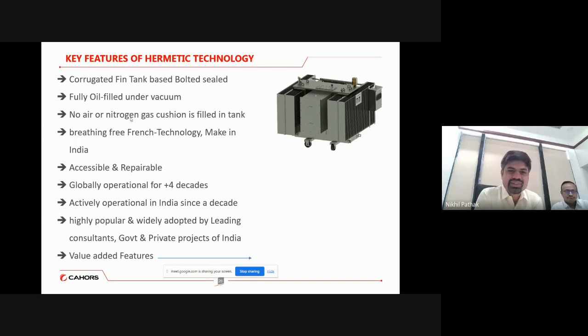Just to elaborate this, basically, I'm sure many people might be puzzling about the expansion area for the oil. So, as rightly said by Sanjay sir, the expansion of oil when it gets heated up, it goes into the corrugated fins and the corrugated fin expands, and it gives more area for the transformer to open up, and more area is given so that the extra volume of oil is equally accommodated and compensated within all the fins which come with these corrugated fins.